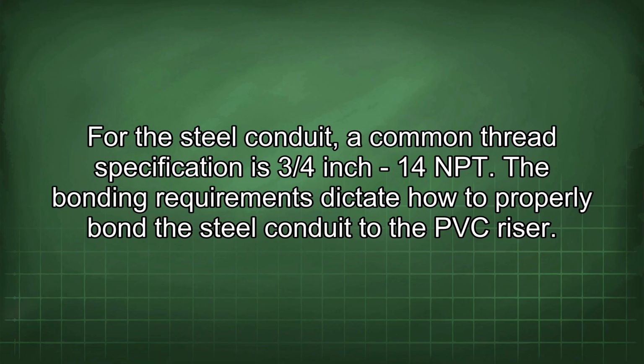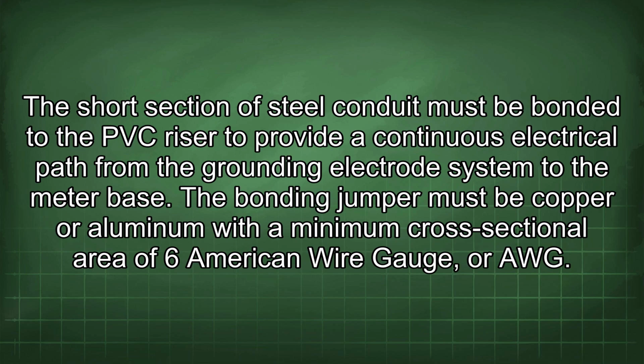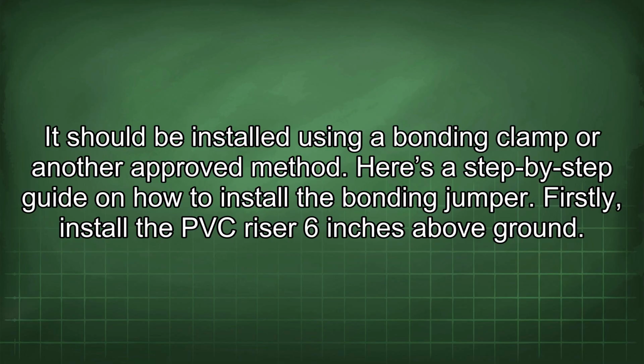The bonding requirements dictate how to properly bond the steel conduit to the PVC riser. The short section of steel conduit must be bonded to the PVC riser to provide a continuous electrical path from the grounding electrode system to the meter base. The bonding jumper must be copper or aluminum with a minimum cross-sectional area of 6 American wire gauge, or AWG. It should be installed using a bonding clamp or another approved method.